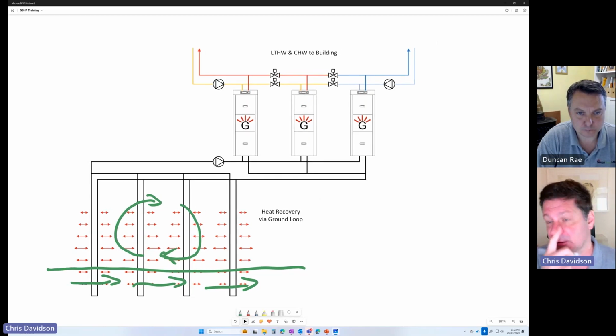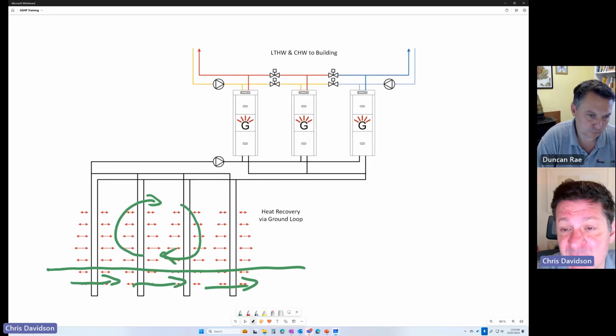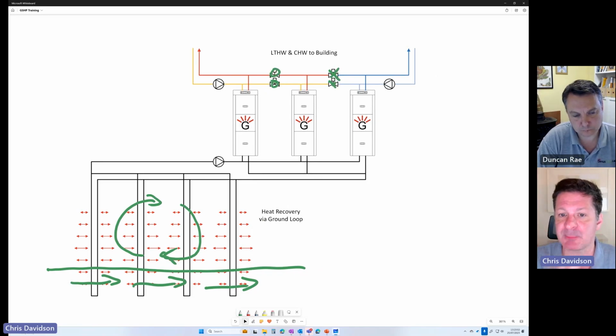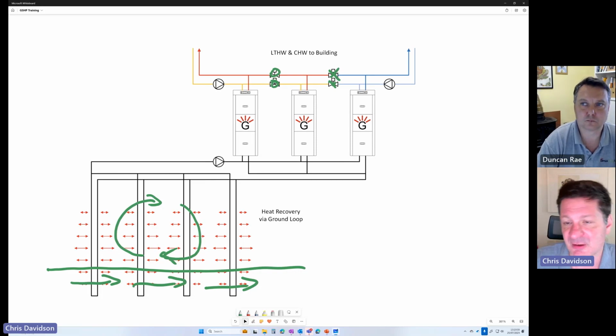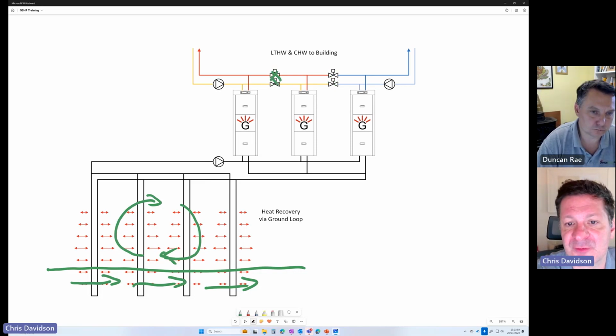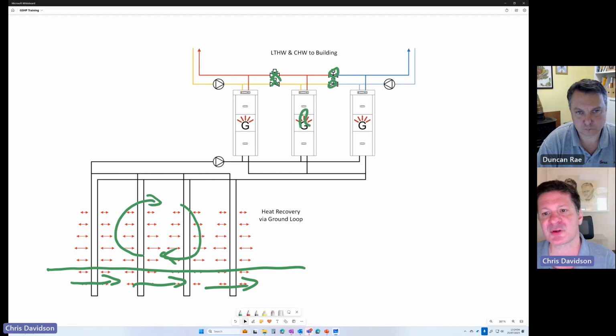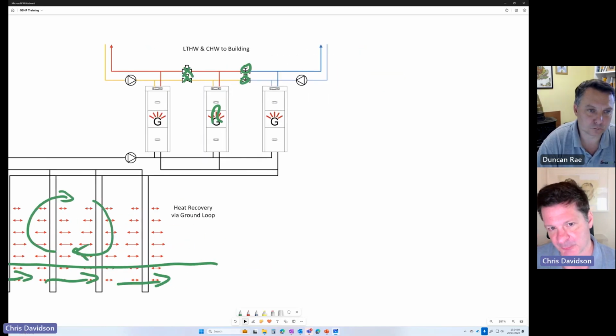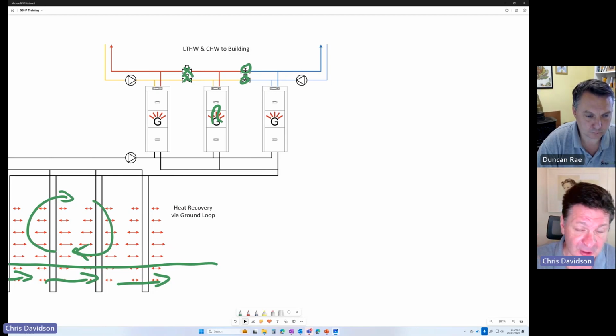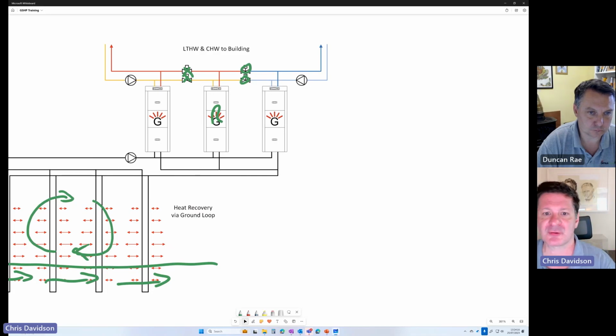So let's now look at what happens. Let's say we are in the winter here, we've got these two valves closed, these two valves open to allow those two heat pumps to deliver heating. Let's say we're moving into the summer now, and so we can close these valves off, open these valves up, reverse this heat pump, and we've now got two heat pumps cooling and one heat pump heating. And the selection of these heat pumps is really very important. We've not just got to understand what the peak loads are for the building, but how that load breaks down, what character that load has throughout the year.